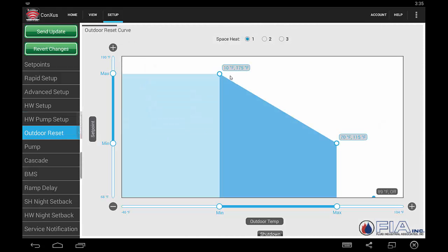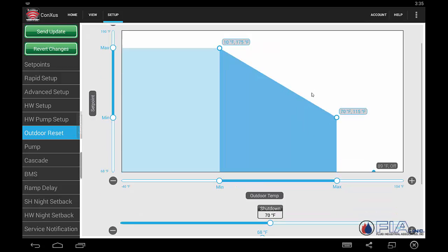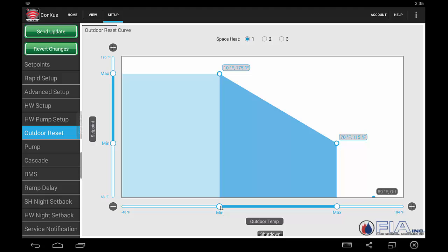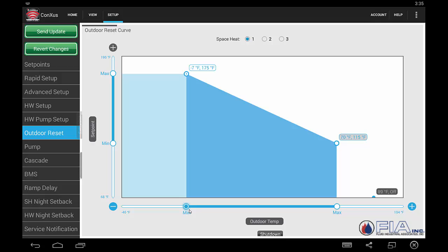Here's our pump setup — how do we want our pump to respond? And in this case, also setting up our domestic hot water recirc pump. Now we can set up our individual outdoor reset curve — each one is done separately: one, two, and three. You'll notice it gives you a look at what your curve looks like all at once, making it very simple. As you make an adjustment, you'll see how that's going to affect the curve across the entire operating range of that boiler.